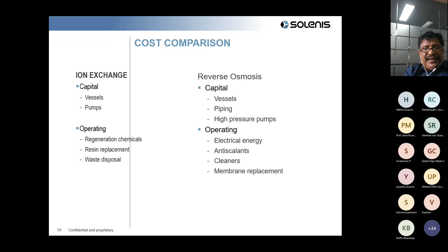And then people decided to go in for reverse osmosis. And this is our simple demineralization. The reason is that we need to have excellent quality at the outlet before it enters the boiler, which is a high pressure boiler. You'll find that the conductivity will be less than 0.1 microsiemens, sodium will be less than 0.01, and the reactive silica will be 0.02.